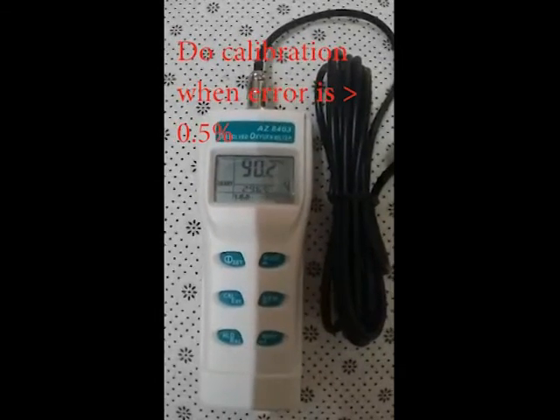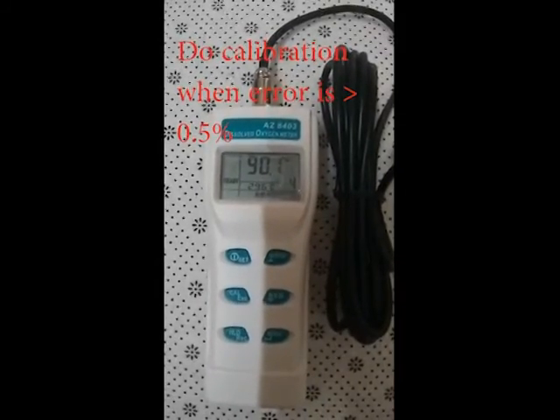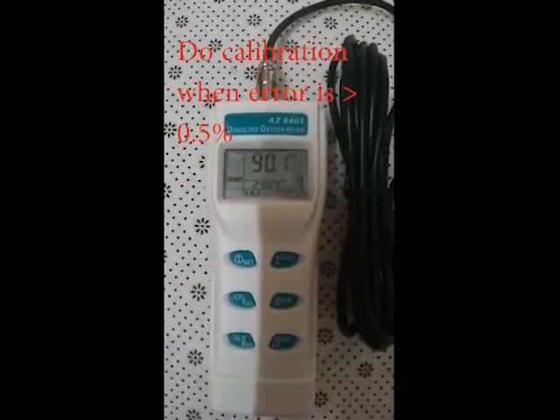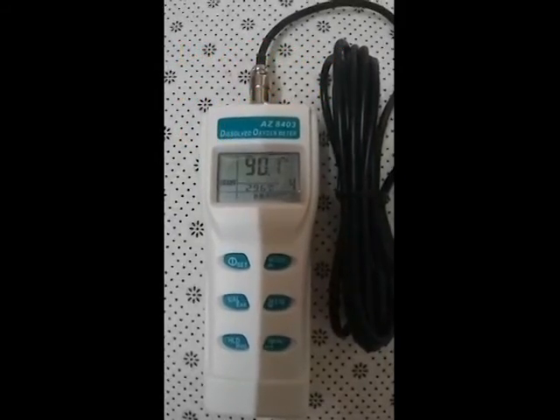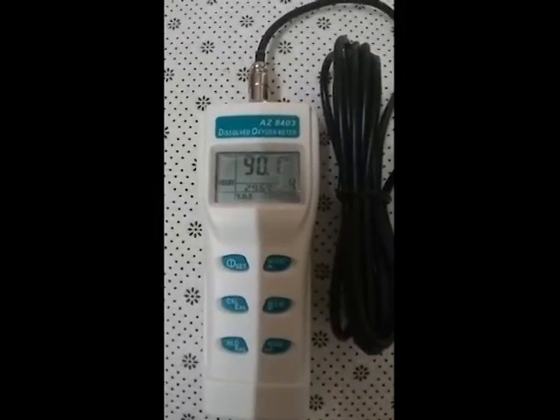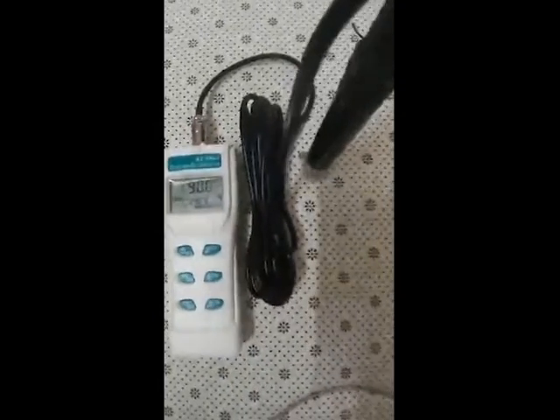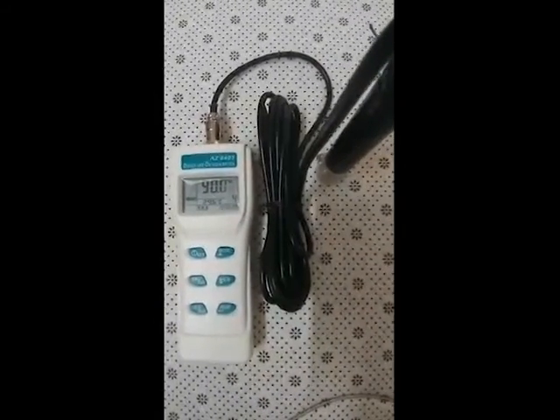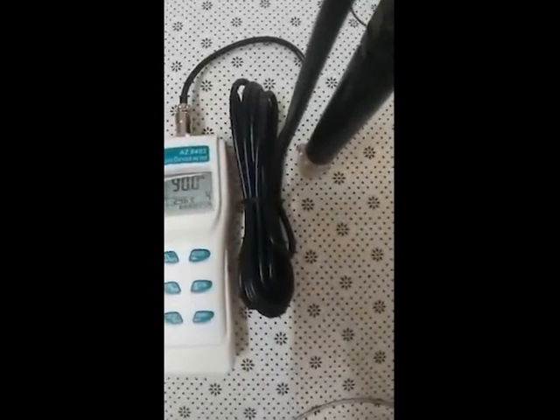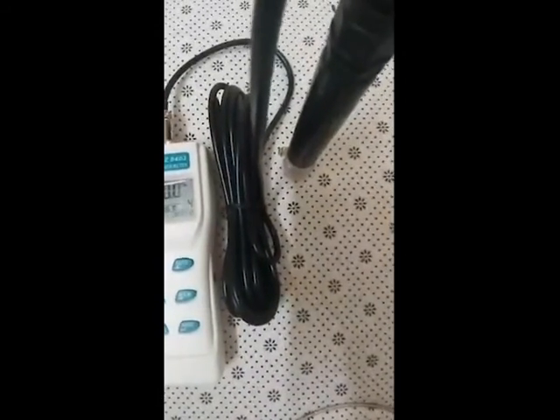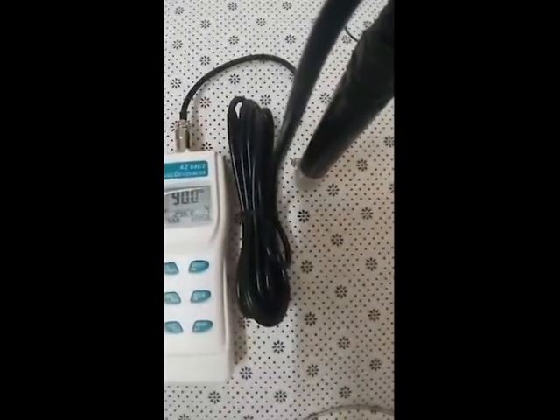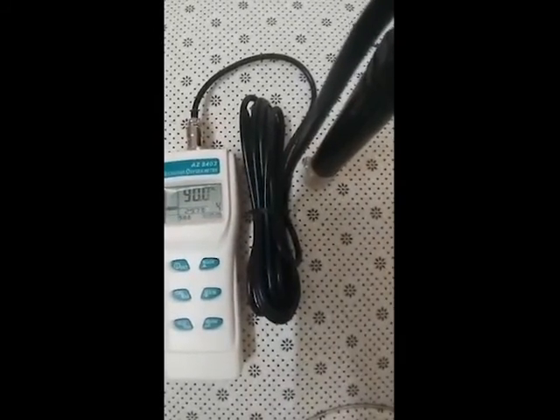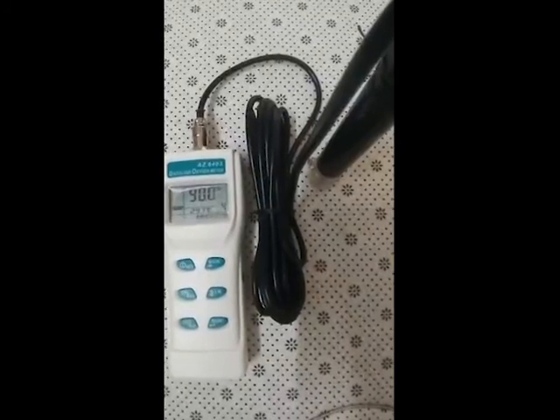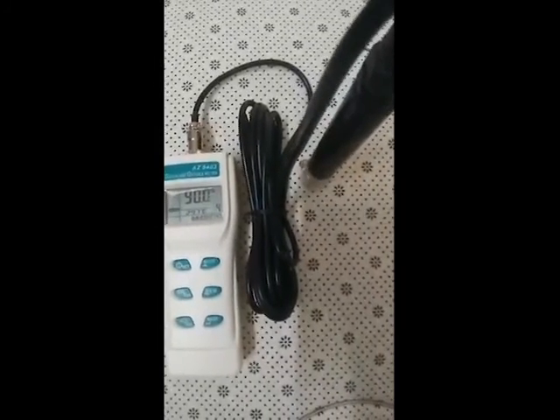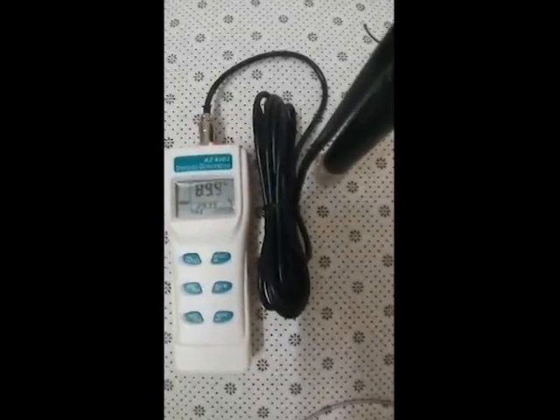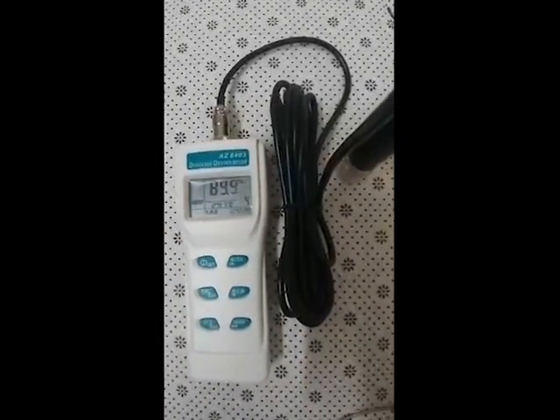At the first time use, when you turn on the system, if you find the error is more than plus minus 0.5, you have to do the calibration. During the calibration, you soak the electrode inside pure water. You can use DI water or pure distilled water, which is much better. Soak it in pure water, rinse it properly, and soak for about 2 minutes. Then you take out the electrode. Then you can start to do the calibration.